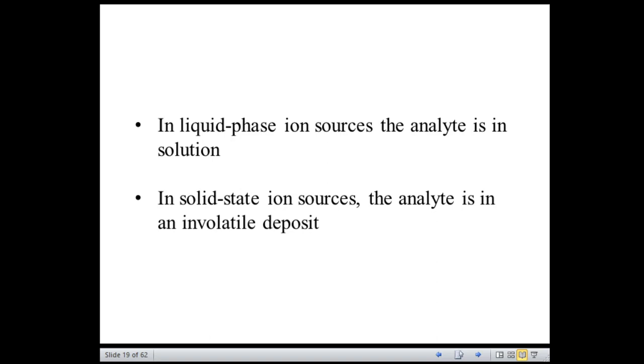What happens in liquid phase ion source, where the analyte is in solution? This solution is introduced by nebulization, that is, as droplets into the ionization source, where ions are produced at atmospheric pressure and they are focused into the mass spectrometer through some vacuum pumping stages. Right? That means the analyte is in solution. So this solution is introduced by nebulization, that is in the form of droplets.